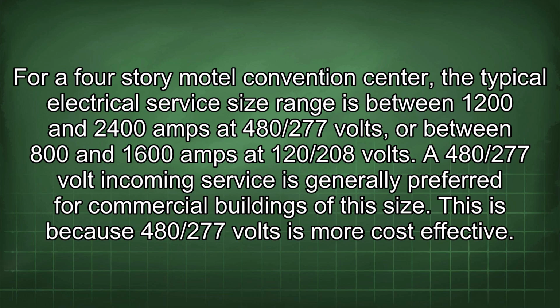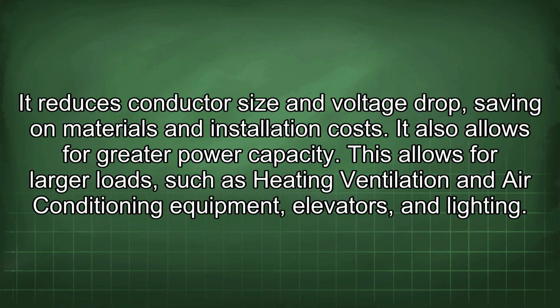This is because 480/277 volts is more cost-effective. It reduces conductor size and voltage drop, saving on materials and installation costs. It also allows for greater power capacity. This allows for larger loads such as heating, ventilation and air conditioning equipment, elevators, and lighting.